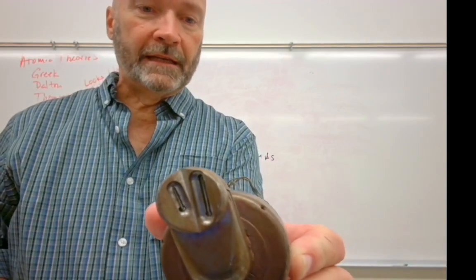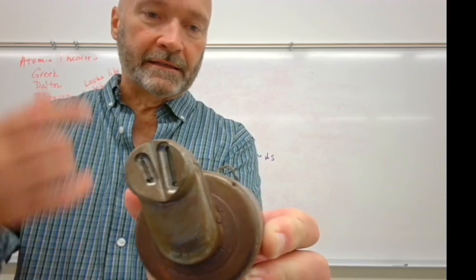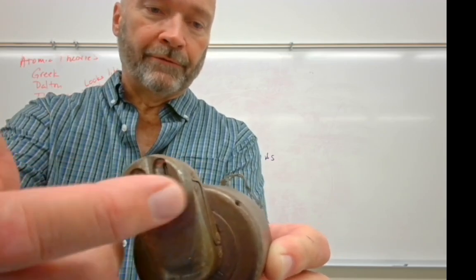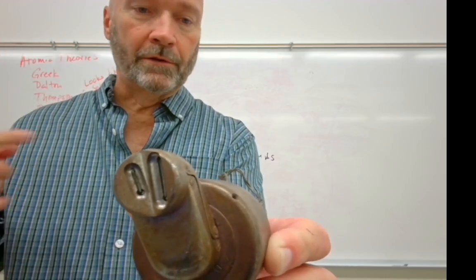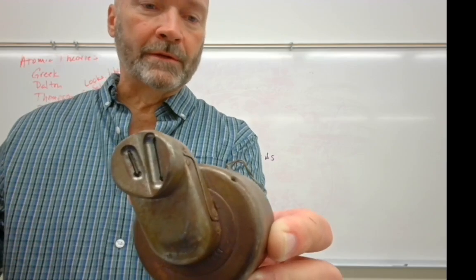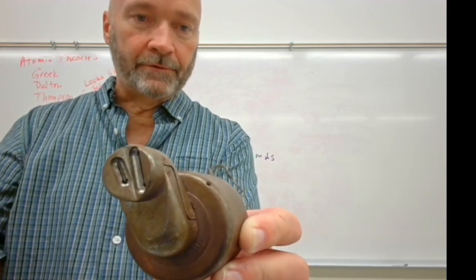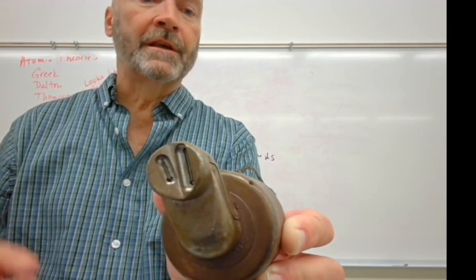The filaments, I told you I'd show you what the filament looked like, and this is harder than it seems like it should be. But you see that this whole thing is what we refer to as the cathode. And I'll talk about the individual components of this, but this has got 2 different filaments, and the filaments are just like a light bulb. It's just real curly wire. So this is where we get the thermionic emissions and where we send the electrons. We send them from this across the tube to hit the anode to create the X-rays. So this is a source of thermionic emissions. This is where we create our space charge before we send them across the tube. So when we hit our prep button, we spin the anode, we heat this thing up.